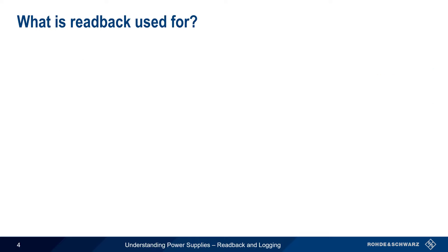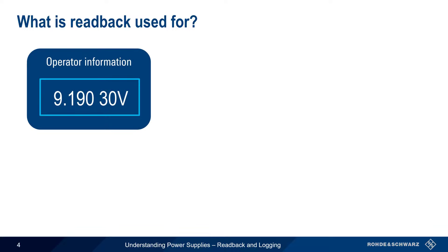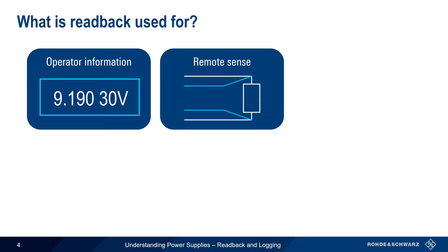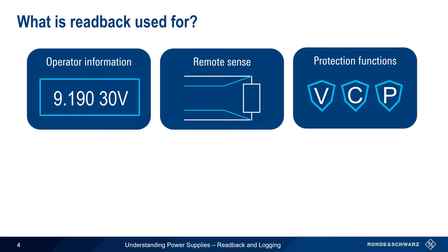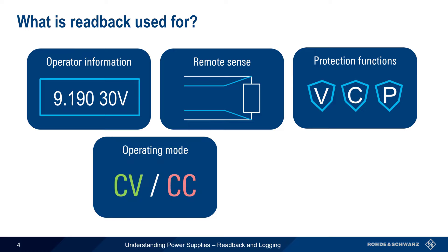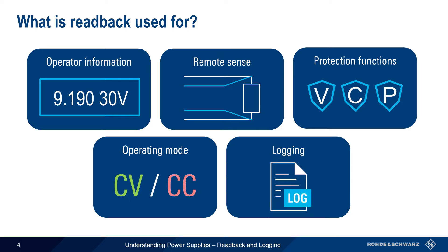There are five main areas in which readback is used. The first is simple operator information — showing the user the values of voltage, current, and power being produced by the supply. Another area is remote sense, which is used to compensate for voltage drop between the power supply output terminals and the load. Protection functions use readback to avoid situations in which the voltage, current, and/or power exceed user-defined or hardware-defined safe limits. Readback is also vital in determining if a power supply is operating in so-called constant voltage or constant current mode. Finally, readback is used for logging the measured supply output values.